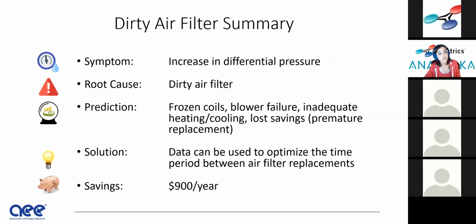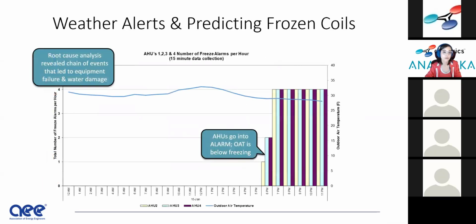Your prediction: you can have frozen coils from this because you don't have enough airflow. You can have blower failure, inadequate heating, cooling, etc. So we optimize the time period between air filter replacements. Savings is only, I say only, $900 a year for this filter, but that's for one filter. Think about 2,000 filters in your building, and also think about what we're not talking about, which is just a more streamlined maintenance program. You're going to save not just in energy, but in people's time. There's plenty of other things they can do on a site.